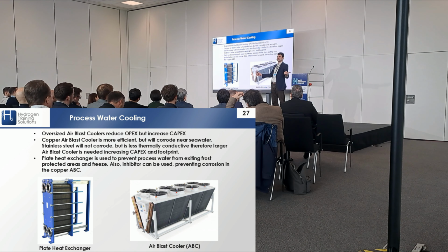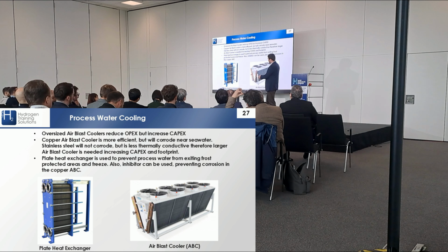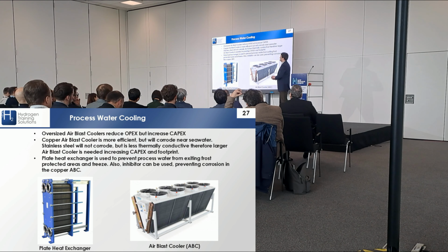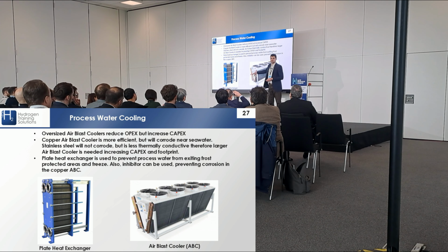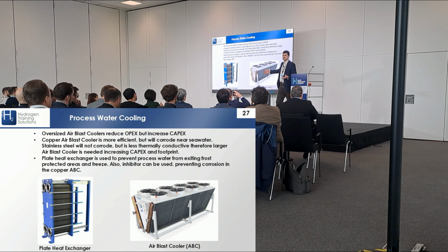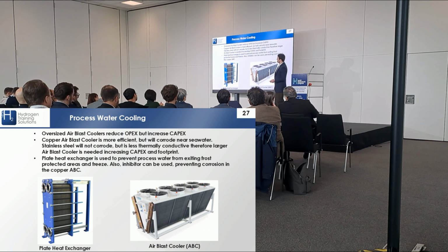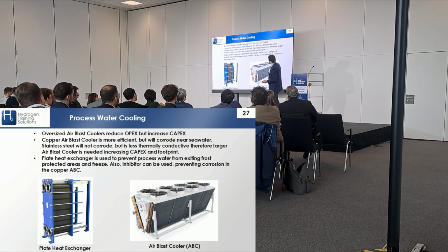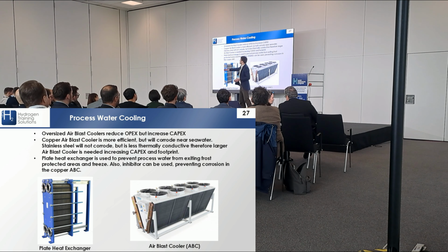How cold does it get in Germany? Does it get -10, -20 in the winter? Yeah, it's going to freeze. So we want this to be filled with cooling medium. A copper air blast cooler is more efficient but will corrode near seawater. So of course this is a copper air blast cooler. You must not have this within 1 or 2 kilometers of the sea because it will corrode. It won't last for a very long time. What you can use in that case, if you're very close to seawater, is stainless steel.